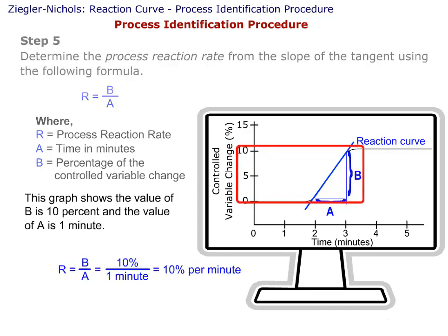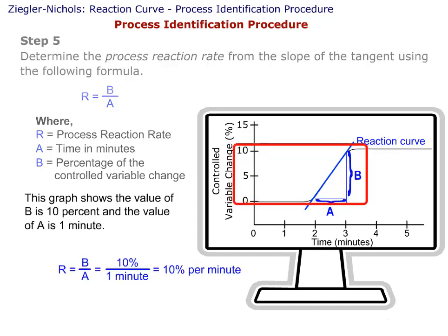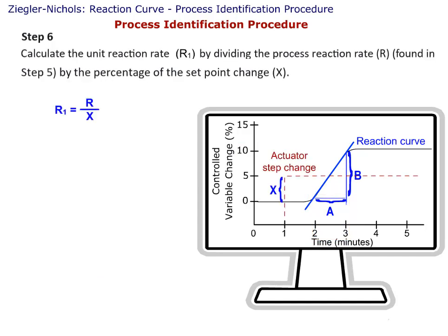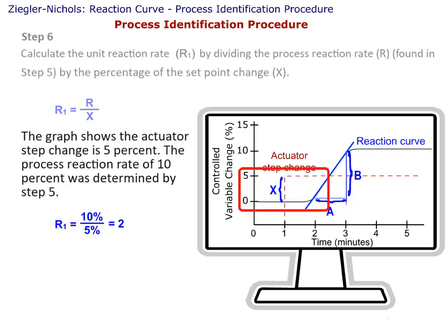This graph shows the value of B is 10 percent, and the value of A is one minute. Step 6: Calculate the unit reaction rate, R1, by dividing the process reaction rate R found in Step 5 by the percentage of the set point change, or X. The graph shows the actuator step change is 5 percent.